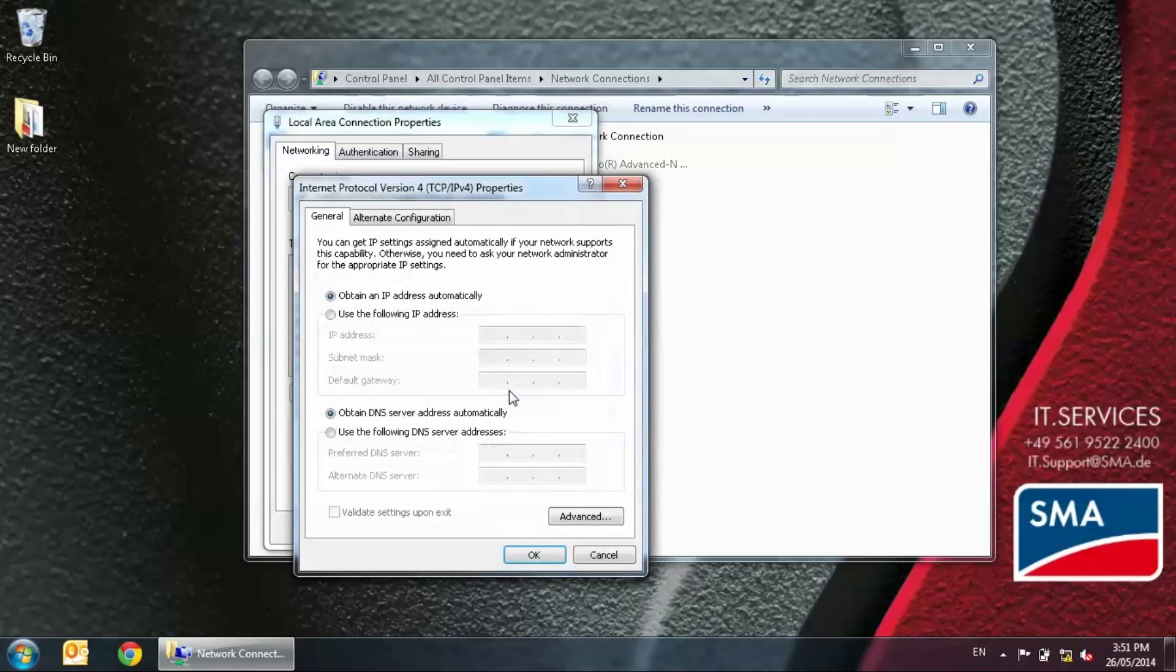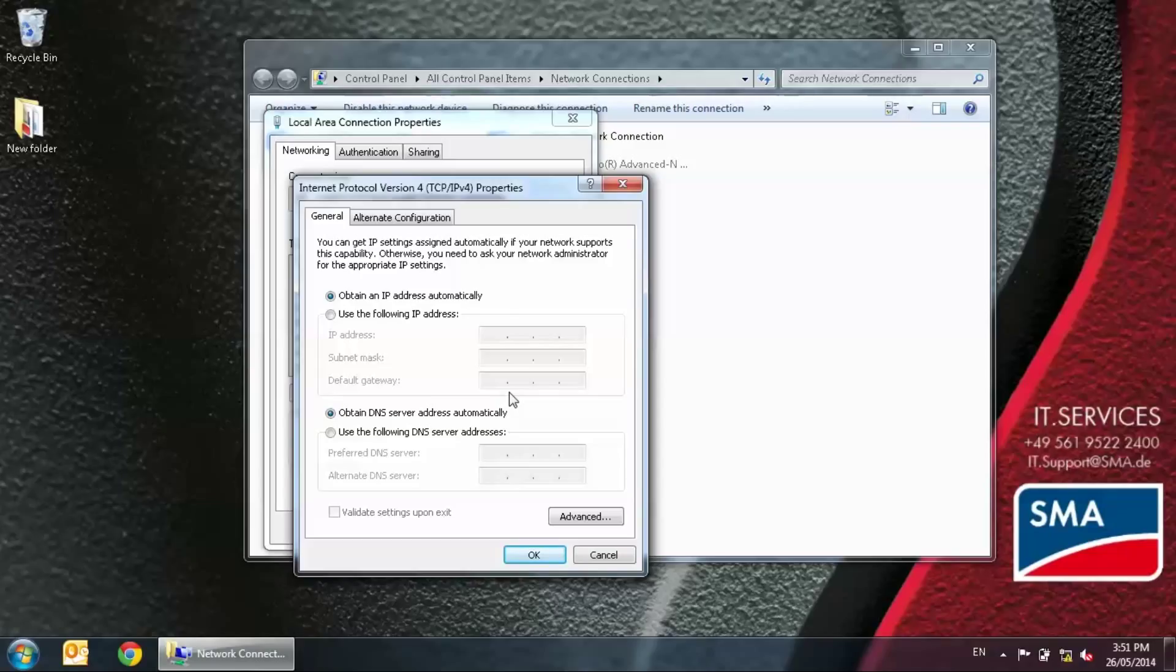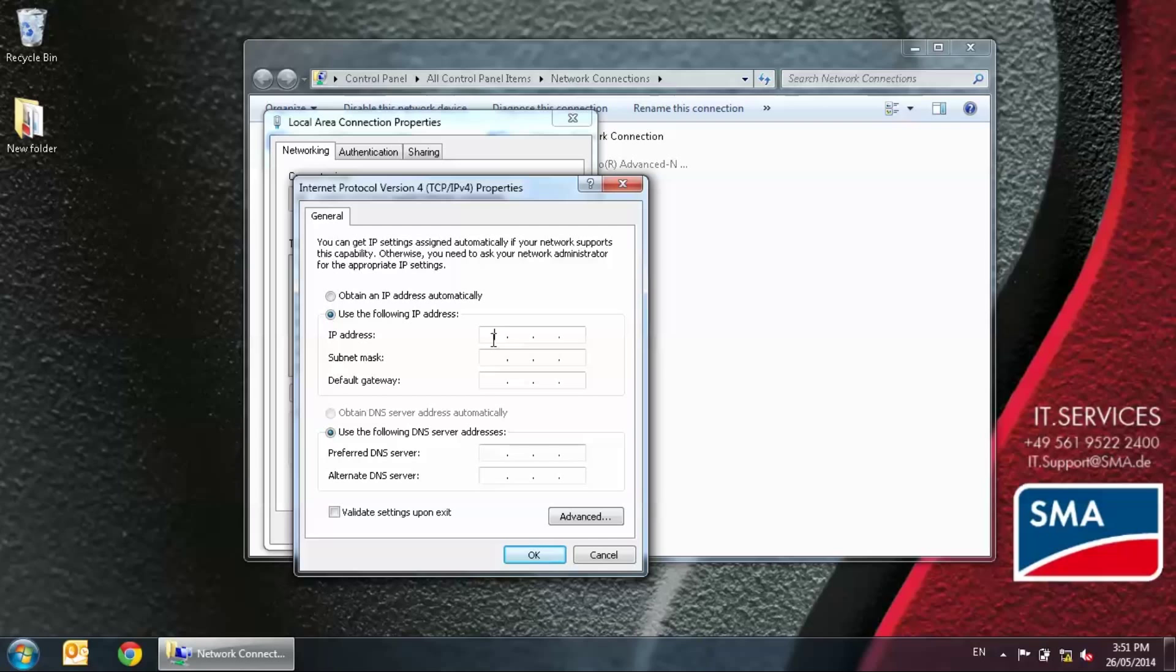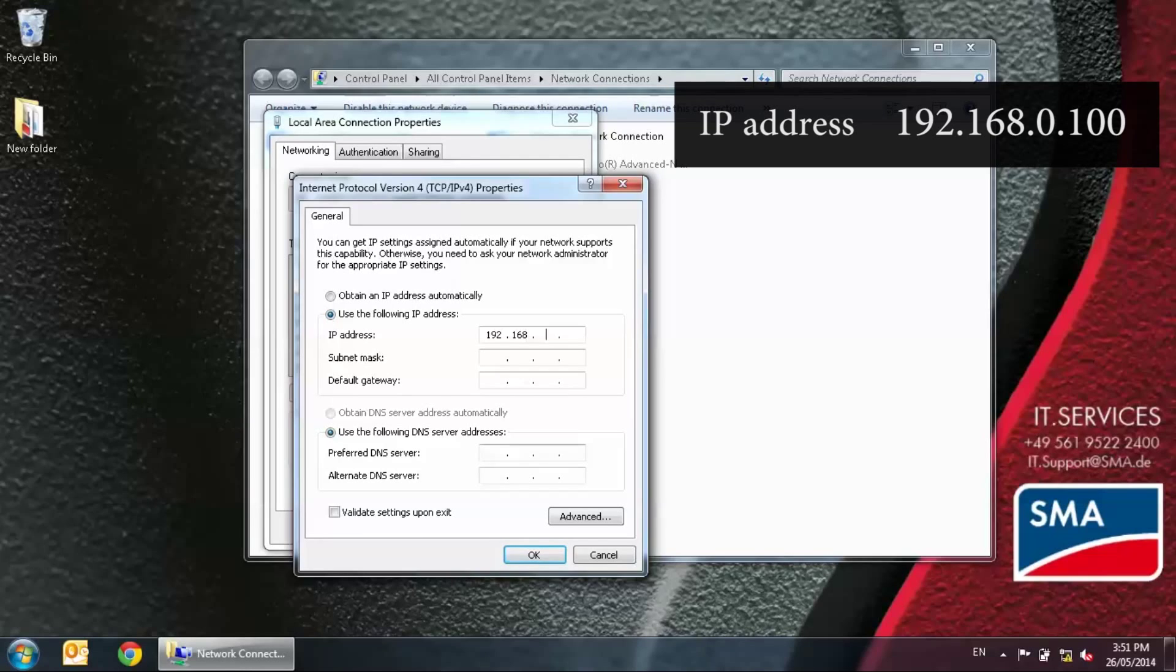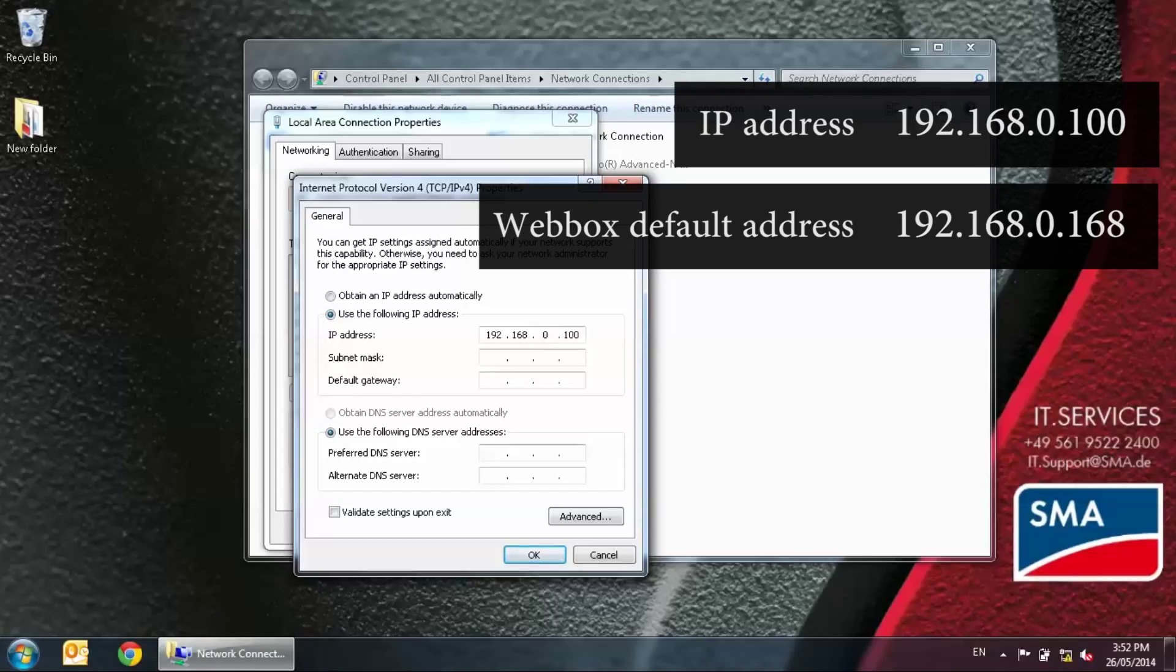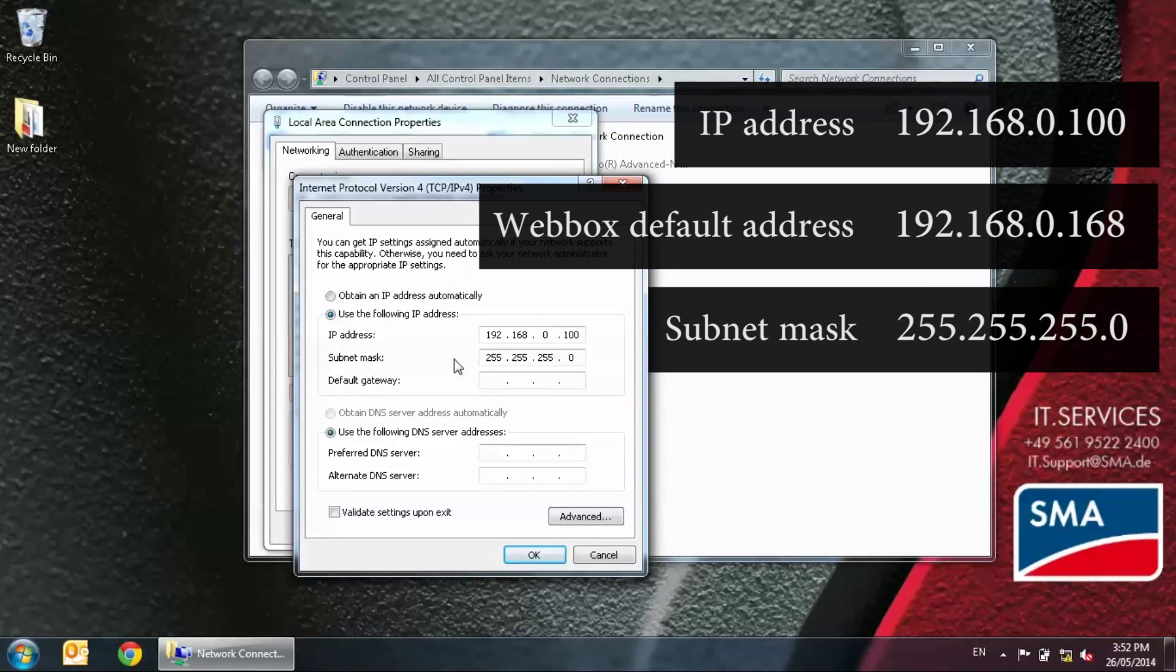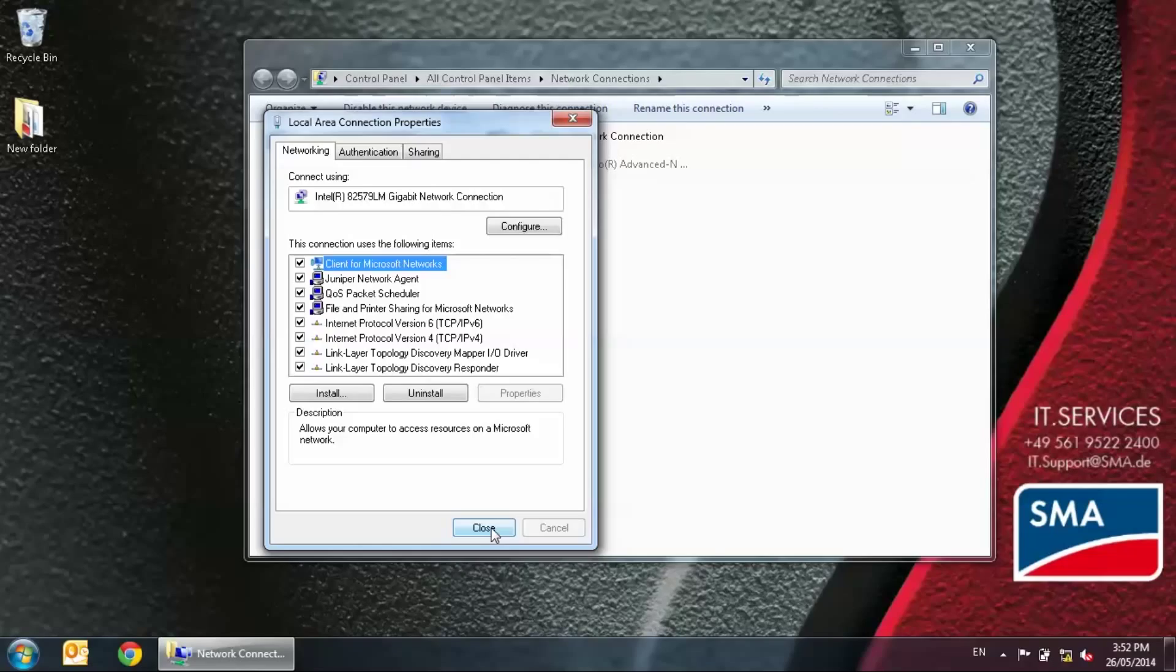Locate and select internet protocol TCP IP version 4 and click on properties. Here you will see that the laptop IP setting is set to obtain an IP address automatically. When the laptop is plugged into a server, the server will allocate an available IP address to the laptop. Here we have the laptop connected directly to the web box so there will be no IP address. Select use the following IP address and put in an address similar to the web box default IP setting. SMA recommends you to use 192.168.0.100. Remember, the web box is 192.168.0.168. We're just making a similar address so it matches to the web box address. Click on the next row and the subnet mask will show automatically, showing 255.255.255.0. The rest are OK. So press OK for this screen and close the other windows.